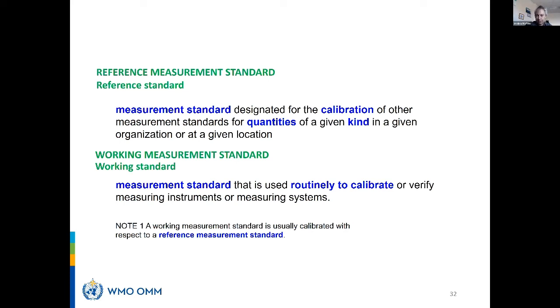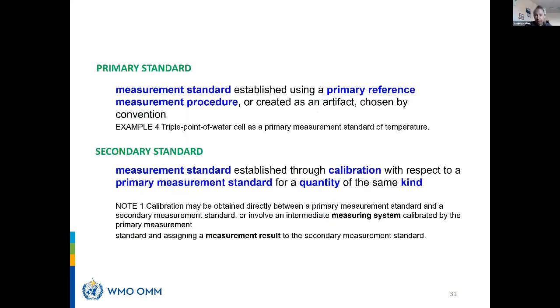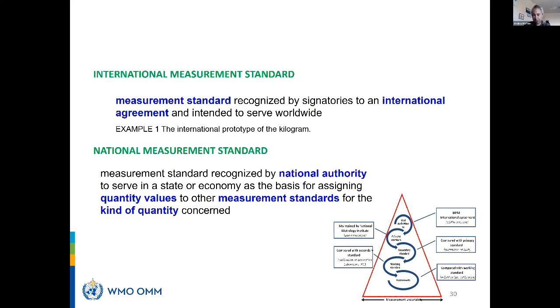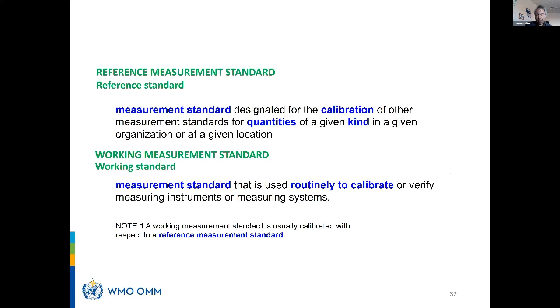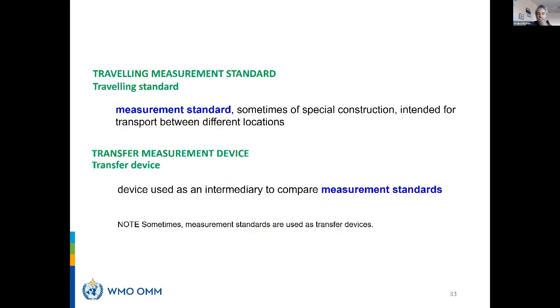And then you have the working standard, which is used on an everyday basis. It costs less. If it breaks, you're not destroying your national traceability or your laboratory's high-level quality, because your laboratory needs to have a primary laboratory standard and a secondary laboratory standard. The primary standard of the lab must be linked to the national standard, which is linked to the international standard. This is the pyramid that you can see down. So even in a lab, you need your primary, your secondary, which may be the same as the reference, and then you need the working standards.